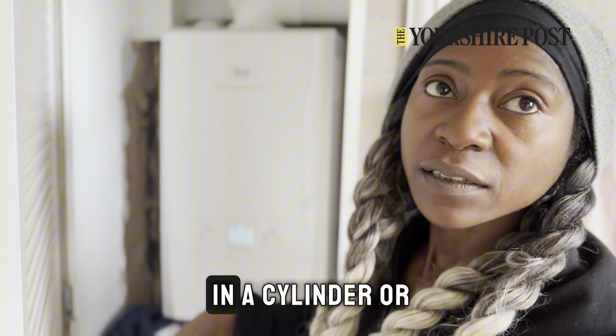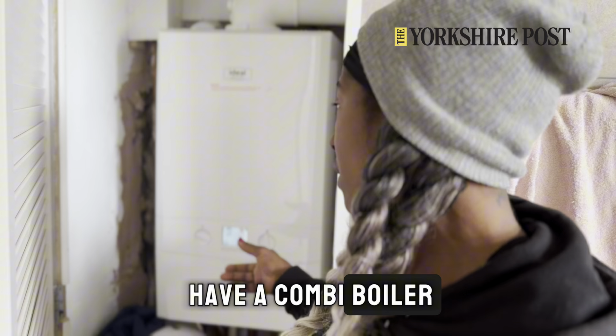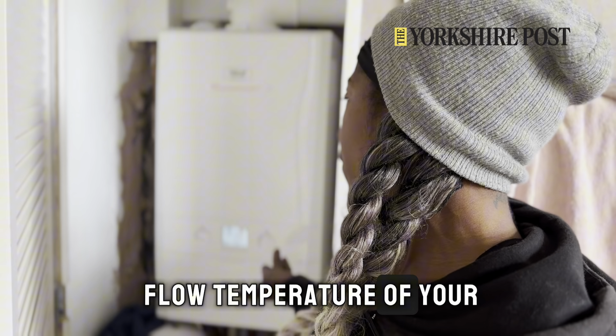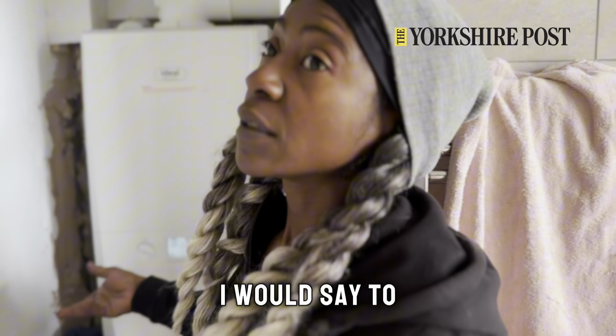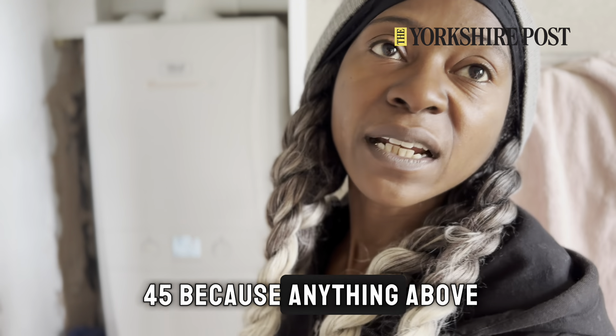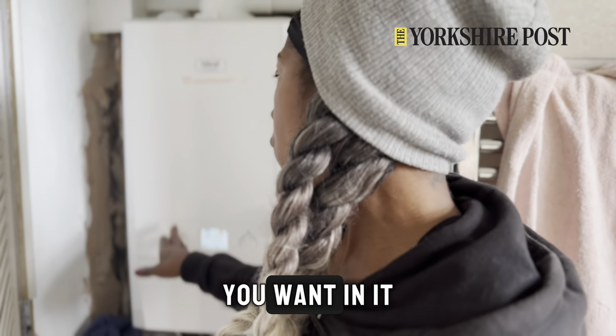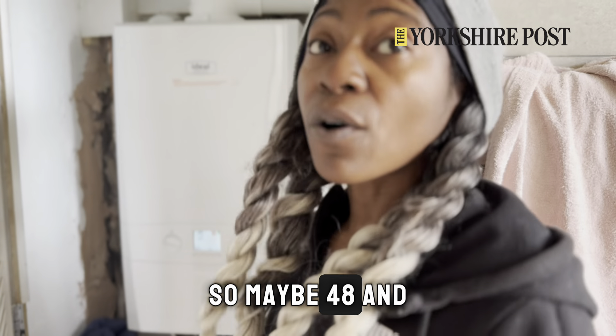When it comes to the plumbing side of things, most people have either a conventional boiler — a boiler and a cylinder — or a combi. If you have a combi boiler, I would reduce the flow temperature of your hot water to 45 degrees, because anything above that you're at risk of scalding. So when you set that, you're wanting it to come out of your taps at about 45 degrees, so maybe set it to 48.